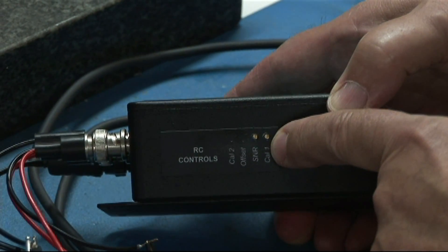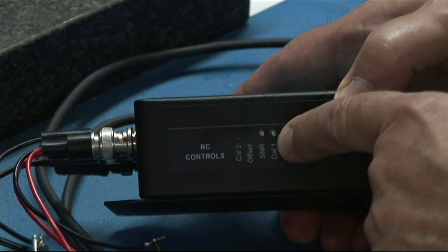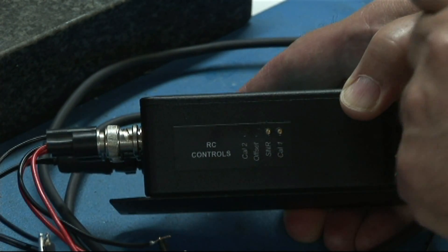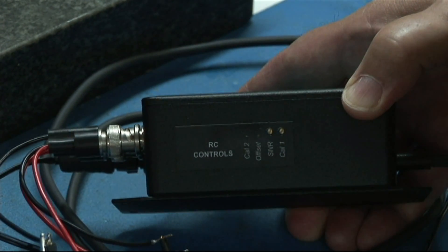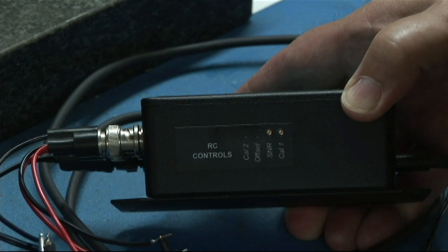Now, the CAL1 control is what we're going to use to set the output of the sensor to be equal to 5.00 volts, when the sensor is gapped to exactly one-half inch.